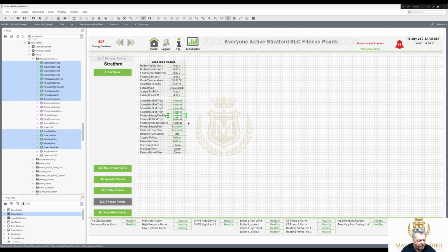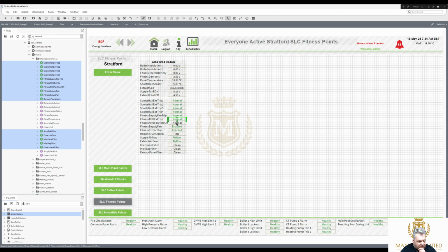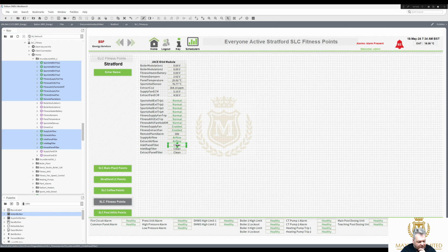But it's acceptable to do it this way. I'm not saying it's wrong. I just don't prefer it that way. If I'm designing panels, I prefer to make all my fail-safes closed to be healthy. I want that as false there. And another one. Put that to that, and that to that. And then we've got the air filters there which are clean, so we need to change them as well.